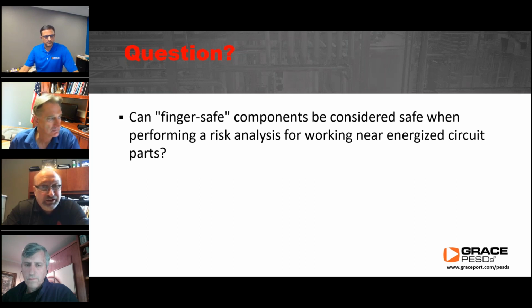So again, this is a question of the qualified person understanding what equipment they're going to be going into energized, and what's on the other side of the door or on the other side of the cover. And if there is finger safe guarding and insulation, and it's completely such that there's no inadvertent movement risk, then there's really no shock risk.